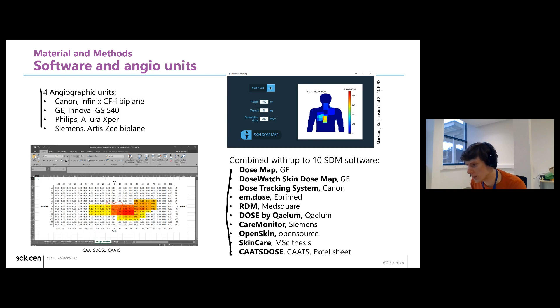And what kind of measurement did we perform? We didn't do anything really particular. We just used a slab phantom and an anthropomorphic phantom. We considered simple configurations, and combinations of simple configurations like repetitions of short clinical procedures. And then we put different types of dosimeters on the table below the phantom, like Gafchromic films, thermoluminescent dosimeters, and a quality control multimeter. Of course, that's not something everyone has access to in hospitals. And then we just compared measurement results with calculations.